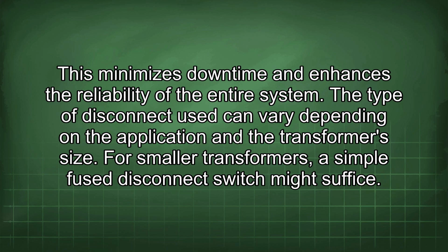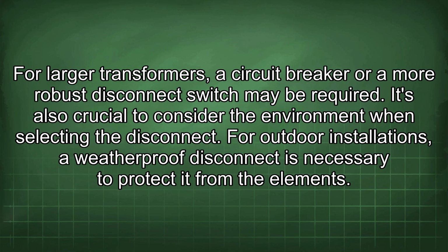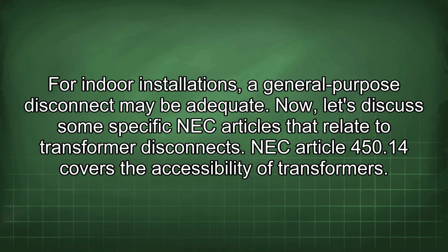The type of disconnect used can vary depending on the application and the transformer's size. For smaller transformers, a simple fuse disconnect switch might suffice. For larger transformers, a circuit breaker or a more robust disconnect switch may be required. It's also crucial to consider the environment when selecting the disconnect. For outdoor installations, a weatherproof disconnect is necessary to protect it from the elements. For indoor installations, a general-purpose disconnect may be adequate.